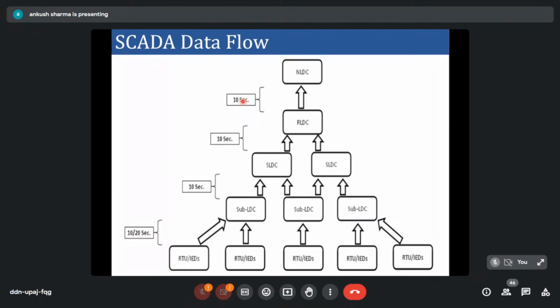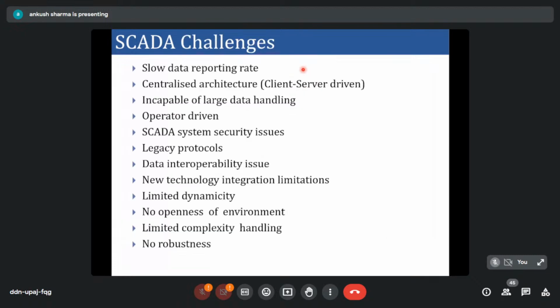So you generally have a very small time window for taking action, and that's why we don't have much real-time visualization with the help of the SCADA system, because by the time data reaches NLDC, the power system state has already changed, and you are getting delayed measurements by around 50 seconds to 1 minute.